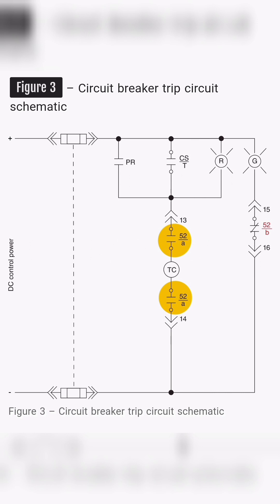The red light is fed from 52A contacts in series and also through the breaker trip coil between the 52A contacts. If you approach this breaker and observe the red light on and the green light off, you will know it is closed, have control power available to trip it, and confirm continuity through the trip coil, verifying the trip coil's integrity. If the red light is off, either the breaker is closed but the trip coil has failed and is open, or the fuse to the breaker's trip circuit has opened. It is crucial to be alert to this condition and raise the alarm. A contact closure from the protective relay PR or the control switch trip contact CS-T will not open or trip the breaker if the breaker is closed and the trip coil is open.